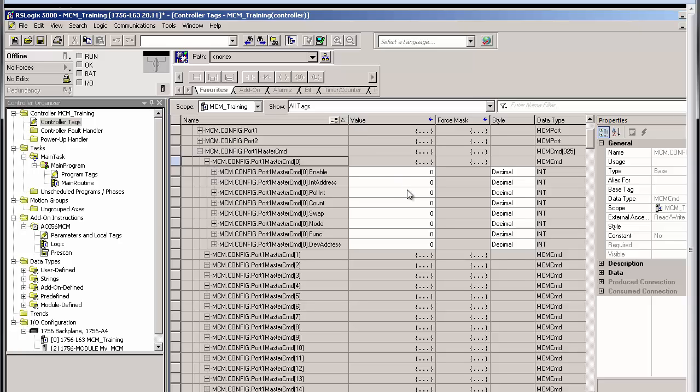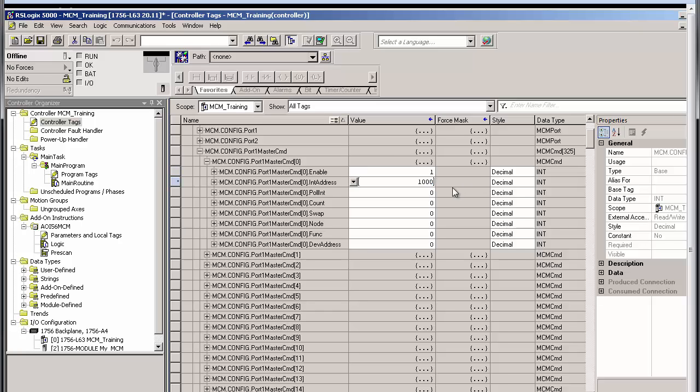Expand MCM.config.port1 master command 0, and under enable, I'll type a 1, which sets the command to run continuously. Next, I'll enter an internal address of 1000. This is where the return data will be placed in the MCM database, which is the starting address for the read data portion of our internal database.